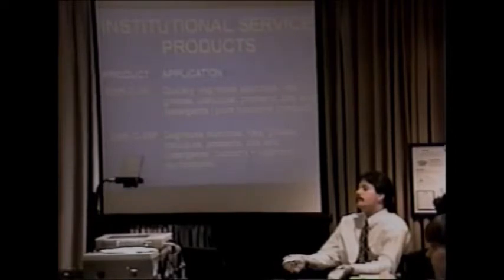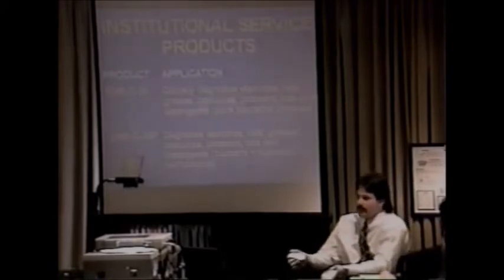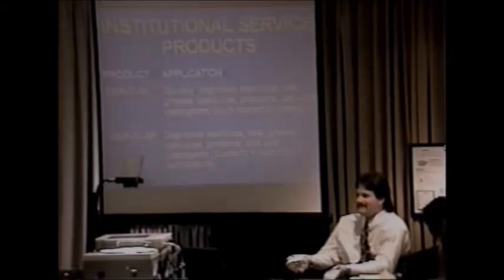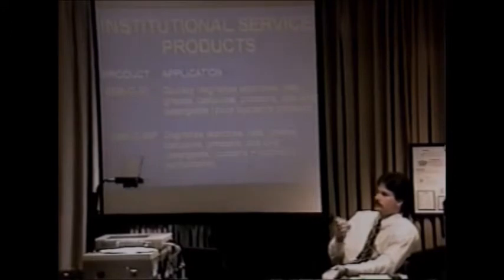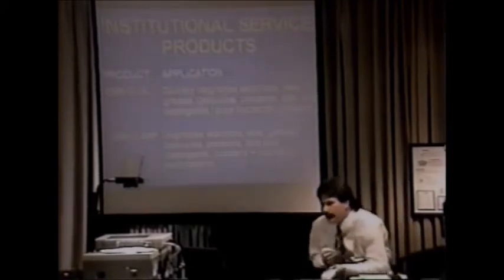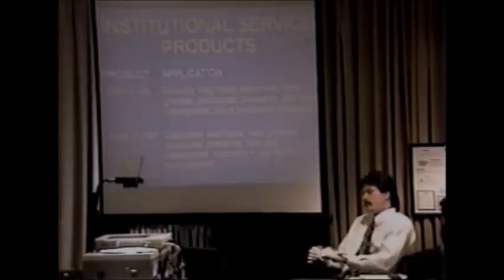You said 1/8 of a pound per what per day? Oh, I didn't finish. 1/8 of a pound per 1,000-gallon grease trap per day. Sorry about that. If it's smaller than 1,000 gallons, do 1/8 of a pound, up to 1,000. Standard grease trap is 1,000 gallons. If you got a big one, obviously we increase that. For every 1,000 gallons, you will go to 1/4 of a pound, to 1/2 a pound. Now, these are the dries. I'll tell you about the system that a lot of people use here after I talk about the liquids.